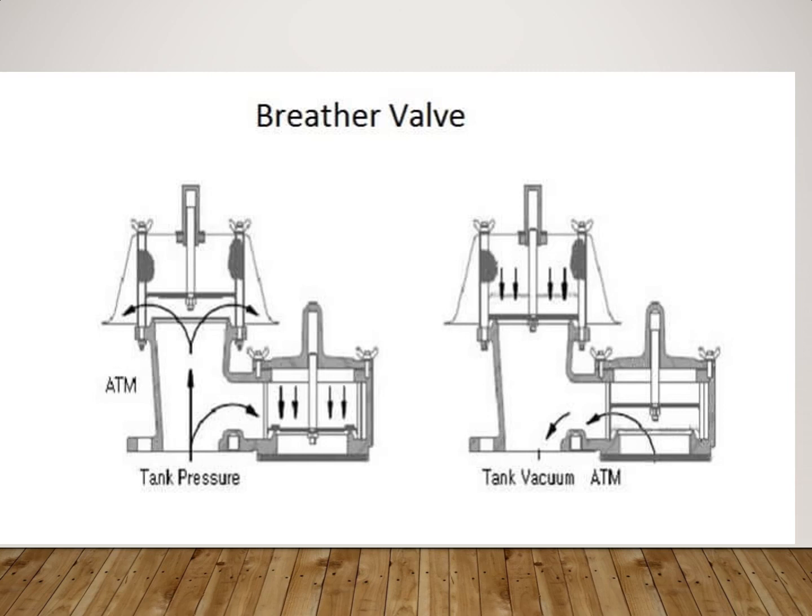The breather valve can be operated for pressure-only condition, vacuum-only condition, and combined pressure and vacuum conditions. The pressure and vacuum sides of the valve have a pallet or diaphragm assembly which rests on the o-ring seal to prevent leakage. The weight of the pallet pushes the diaphragm against the seat to keep it in the closed condition. Hence, the breather valve prevents build-up of excessive pressure which can unbalance the system or damage the storage vessel.